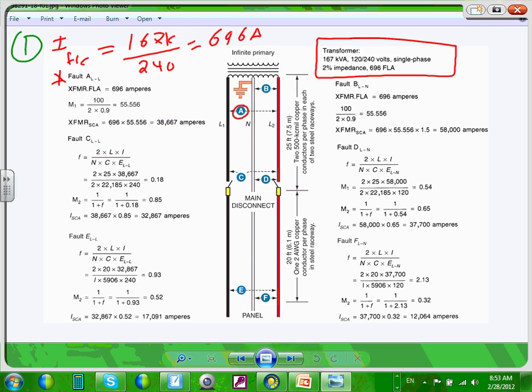Okay. Based on this information, step number two is finding the short circuit right now here. I want to find the short circuit right at point A, which is at the terminal of the transformer. Here's my transformer, guys. I want to take the two hots and tie them together right at the terminal of the transformer and flip the switch on. That's the worst scenario that could ever happen to you, right? If you do that, then here's how you find the short circuit.